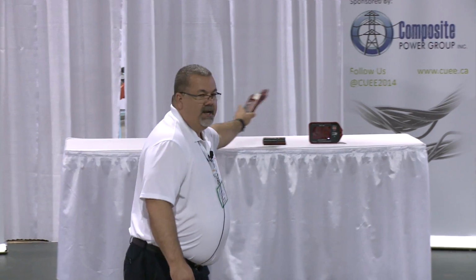Where it becomes important is that I want to know if all 3 phases in an overhead system are energized, or if maybe I've got one that's out. When I'm using something like the V-Watch, which measures voltage at a higher detection rate or higher sensitivity, it would not work in this application, because if any one of the 3 is energized, it's going to tell me that yes, something there is energized. So now I have to have the ability to select the range of voltage that I'm expecting to be there and indicate.